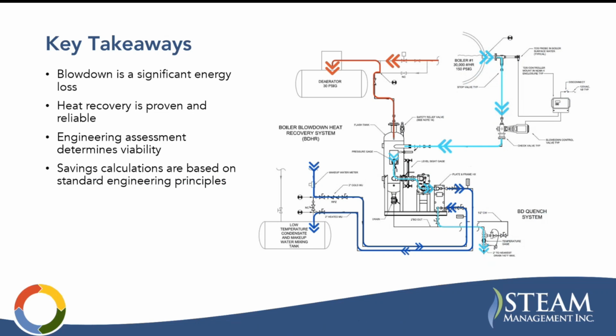Okay, so here are the key takeaways. Blowdown is a significant energy loss. Heat recovery is proven and reliable. Engineering assessment determines viability. As we've gone through this, you see there is some engineering required here. It's not, "Well, I've got a 700 horsepower boiler, so I'm going to put in this size blowdown heat recovery, and I'm generally going to get this." It's not a table lookup. Although it can be, you're not going to get detailed or expected results from that.